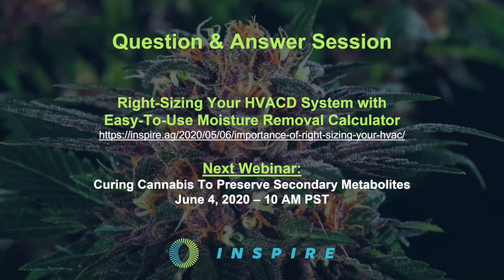So when it comes to this airflow delivery, it's really about making sure of two things: that the air is the appropriate temperature and humidity, so it's conditioned, and also that the rate of airflow, the actual velocity in which it's delivered to the plant, I think our studies show somewhere around a meter per second. I could be wrong on that, but we've done some in-depth data and studies, just to get an idea of how much airflow we need to apply to that leaf surface to positively affect the plant, to break the boundary layer and deliver that CO2, without any stressors, without any leaf curl, without any negative reactions to the environment. And it's just key that that air is conditioned and delivered at the right velocity to avoid that kind of stress. Hopefully that's a little bit of insight on that concept.